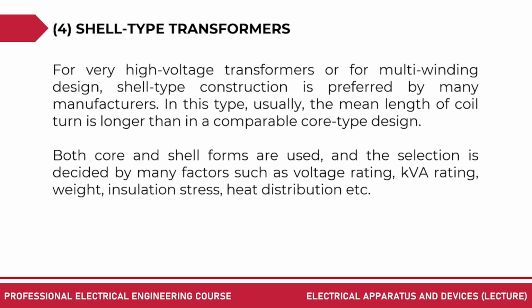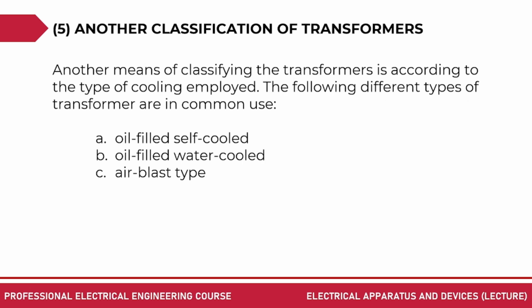For very high voltage transformers or for multi-winding design, shell-type construction is preferred by many manufacturers. In this type, usually, the mean length of coil turn is longer than the comparable core-type design. Both core and shell forms are used, and the selection is decided by many factors such as voltage rating, kVA rating, weight, insulation stress, heat distribution, and etc.